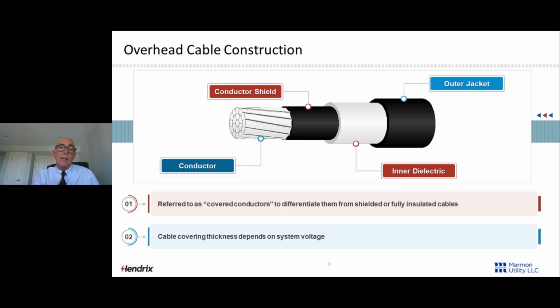The inner dielectric, you can see it's white there. It's translucent. It's a very high BIL, high 60 hertz withstand, low density, high molecular weight polyethylene. The other thing that gives us is we use a really soft, low density so that we can facilitate stripping for taps and junctions and transitions, if you will. You put the knife in through the outside layer and it strips off with that soft inner layer.